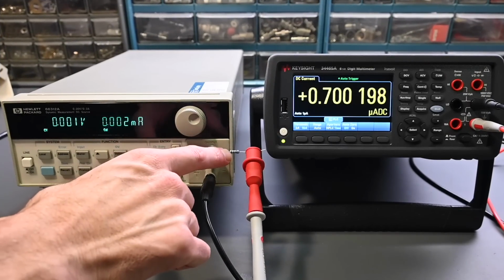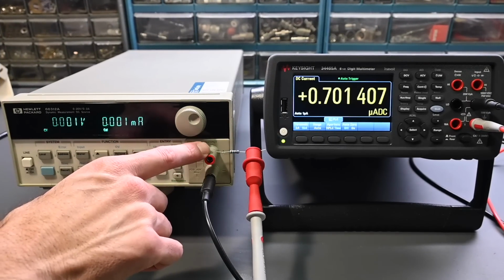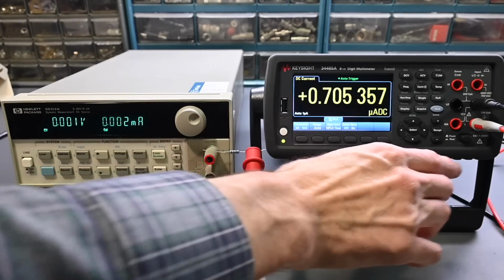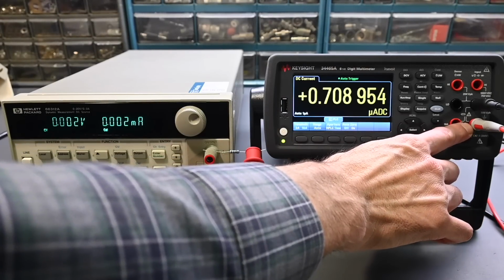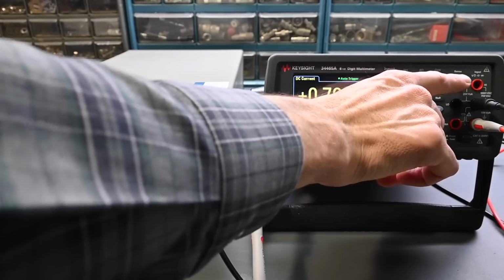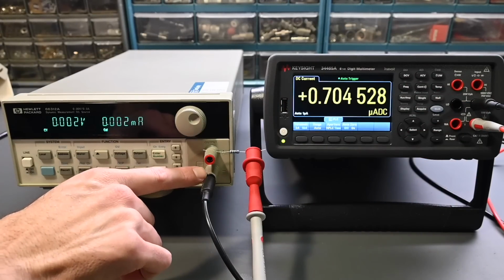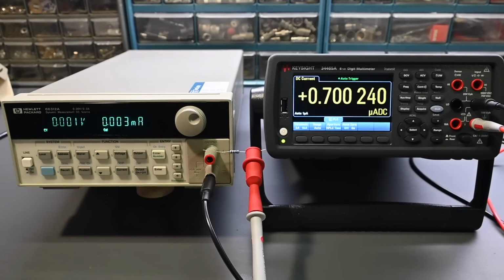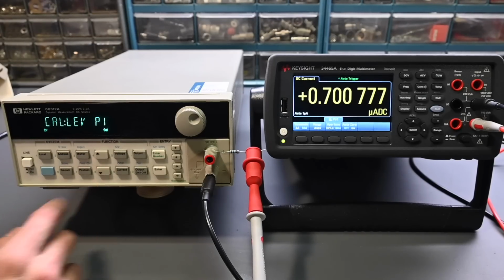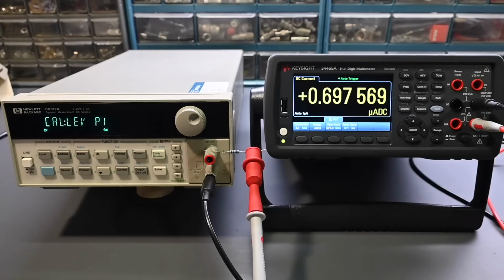All right, I have the 1.1 k ohm resistor installed, so it goes from the positive output of the power supply. It's clipped onto this red test lead. The red test lead goes over here to the positive input on the digital multimeter's current input, and then the black test lead returns back around to the common and negative on the power supply over here. Okay, so let's continue on with the calibration. It says here to make the connections. Okay, we did that. Press Shift Cal, and then scroll to cal level. It says cal level P1. Yep, we're on that. Press enter.